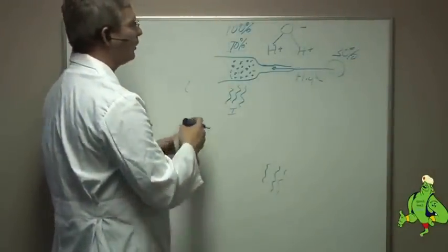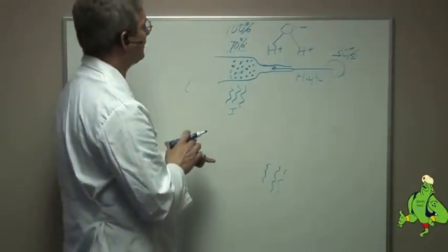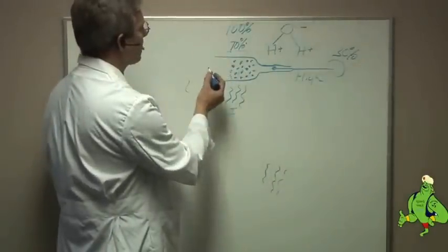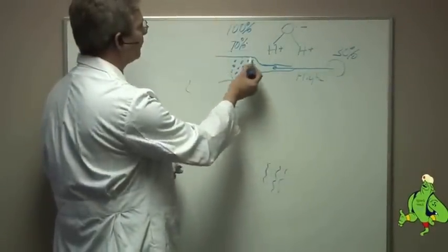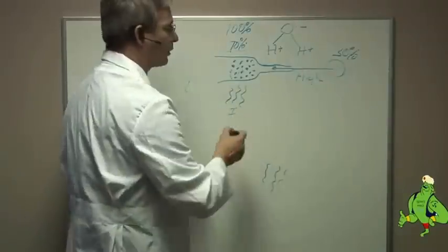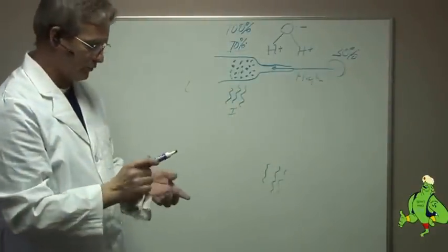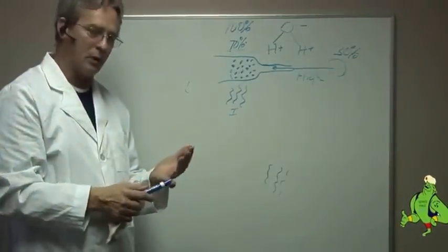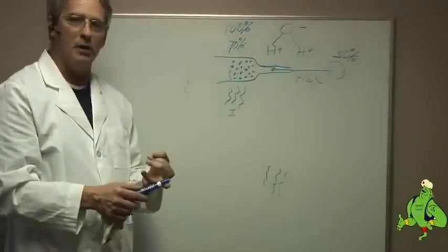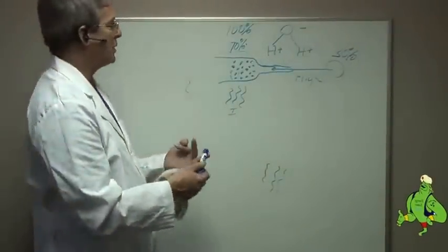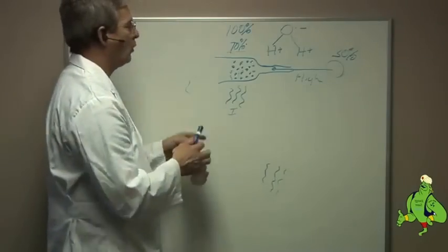So, I know it's all confusing and I'm trying to do this really fast, but our whole goal here is to somehow get rid of this moisture in this entire system because it is a closed system. All right, the moisture went in when they put in the Freon, the moisture went in when they put in the oil, the moisture went in when they built the system. There's no way to evacuate it all out. You can't boil the whole system out.